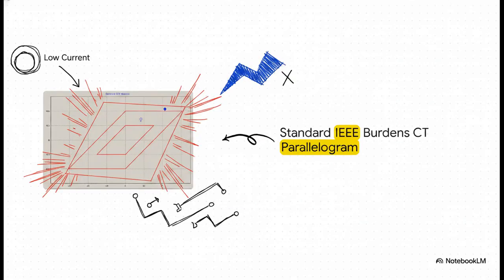Now, what's really interesting about this is how these out-of-class errors are visualized. This parallelogram maps out the IEEE CT metering accuracy limits. That inner box, that's your standard 0.3% class, and the outer one is the 0.6% class. If your calculated burden pushes you outside those lines, well, your metering is out of class and totally inaccurate. And more importantly, this proves that standard metering CTs have absolutely no accuracy guaranteed at current levels less than 10% of their rating. Simply put, low current completely ruins your accuracy.